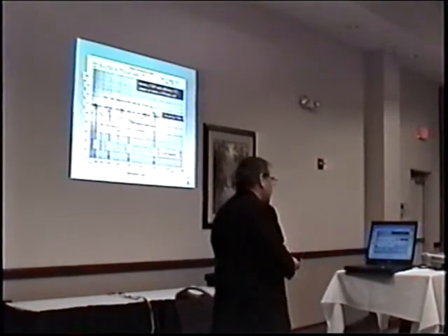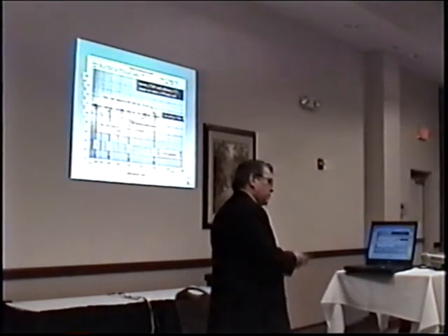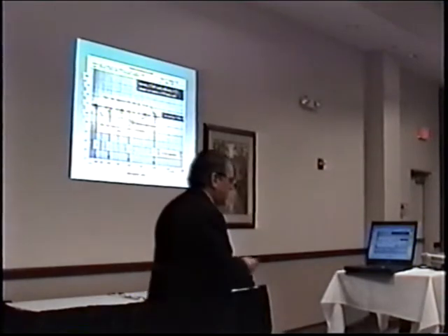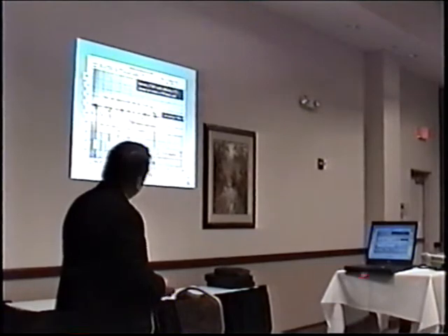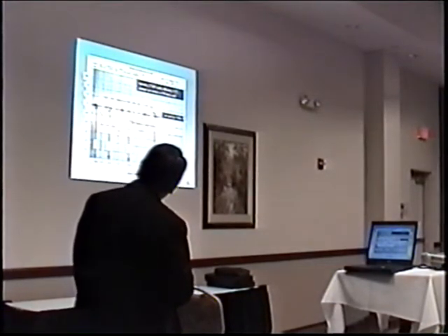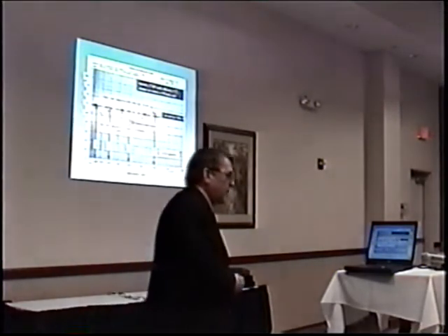So the next test, instead of doing that, everyone in the room except me decided that they wanted to do a test without the accumulator. So we did a test of the next system without the accumulator. And for some reason, it went up to 130 bar. And yet we had methodically and painstakingly set everything at 110 bar.